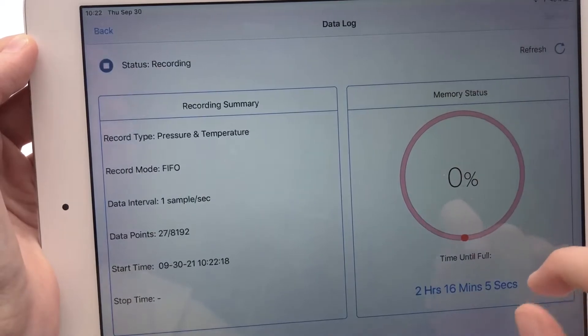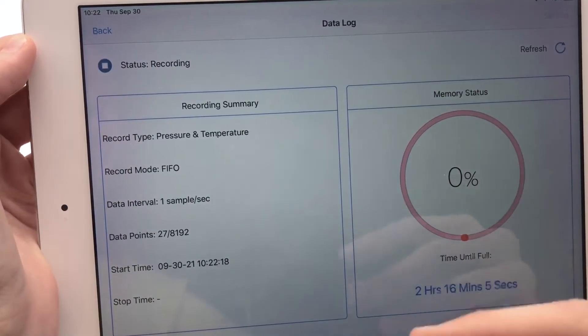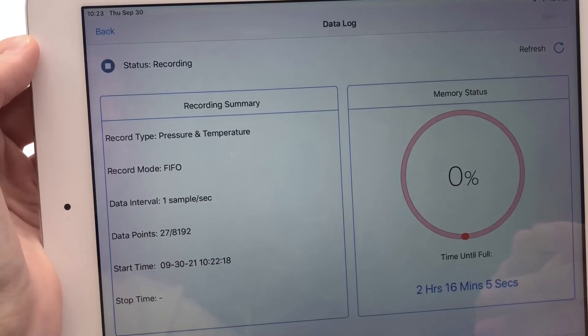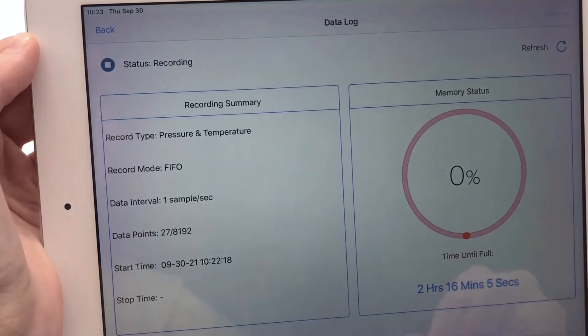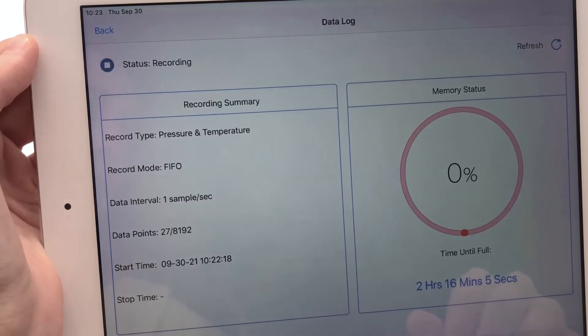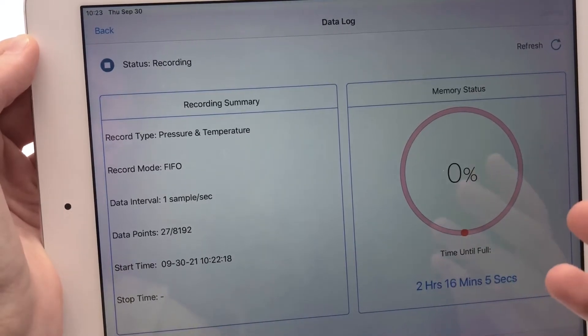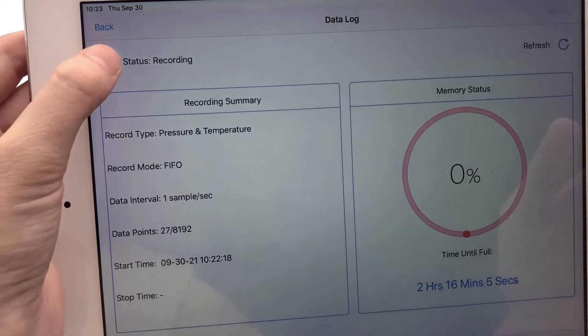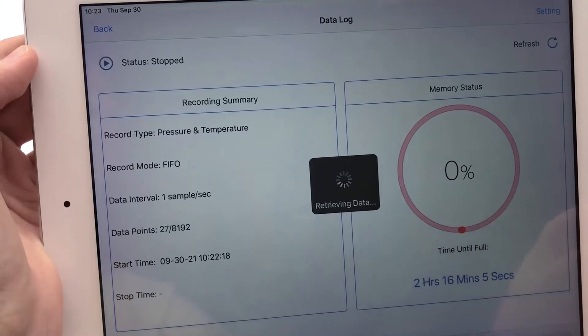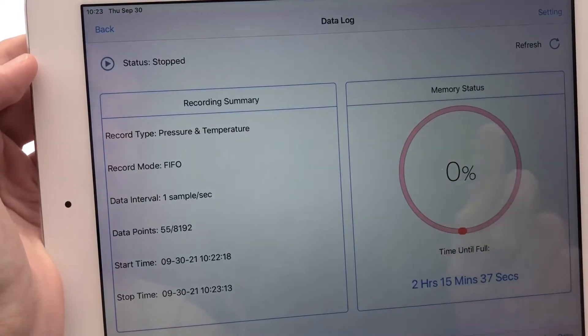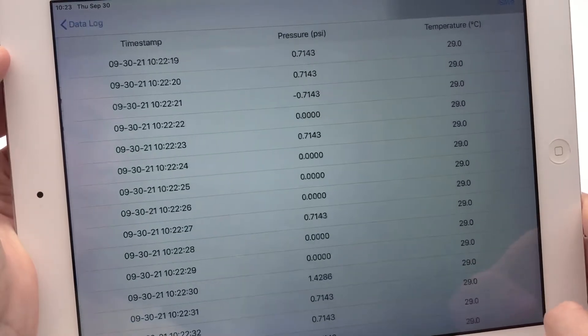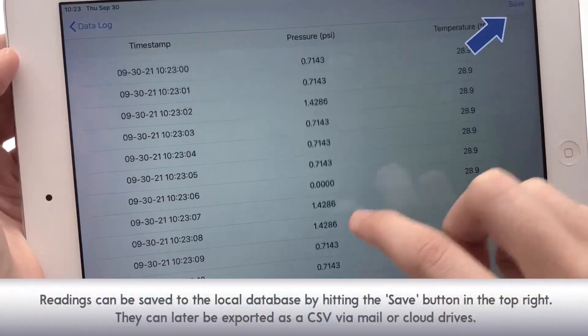Let's go back to that data log page. You can retrieve data either with or without stopping data logging. Be aware that new readings won't be recorded during data transmission if it's triggered during a data logging session, but you can retrieve it while it's logging or after it's logging. Let's stop data logging here and retrieve data. And then once the data is retrieved, you can click over here in the bottom right to view the data.